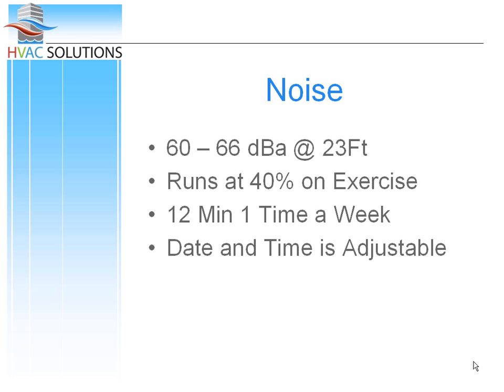Noise, I'll say 60 decibels generally speaking. These ratings are always weird because they're measured far away, like 23 feet, in an open field, which really isn't the Chicago home or suburbs. One nice thing about these units is they run at 40% power during exercise mode, so they're not running full-blown loud. When they do run, it's for 12 minutes once a week, and the time and date are adjustable, so you can set when you want that thing to come on. Sunday at midnight is probably not the best time.